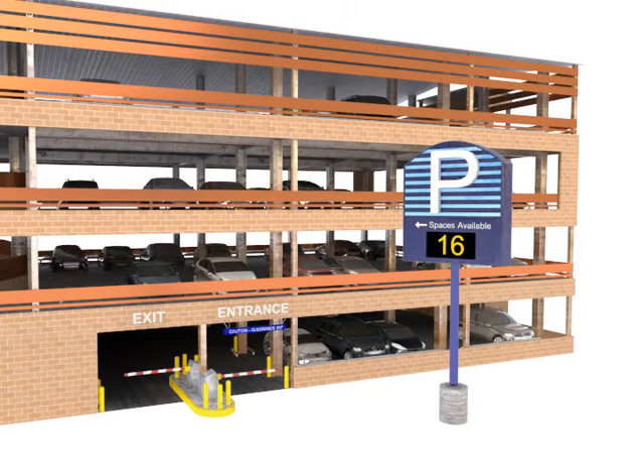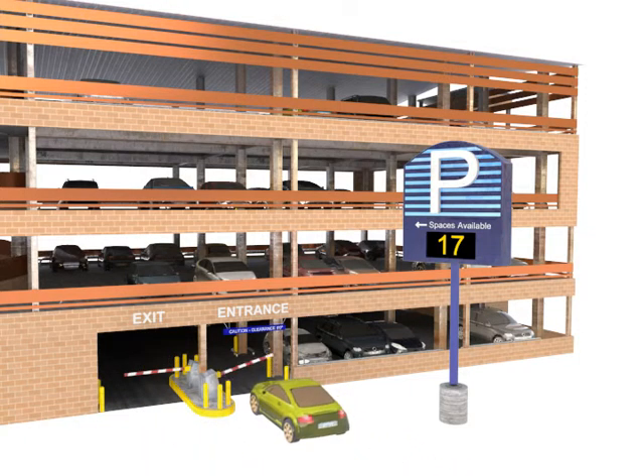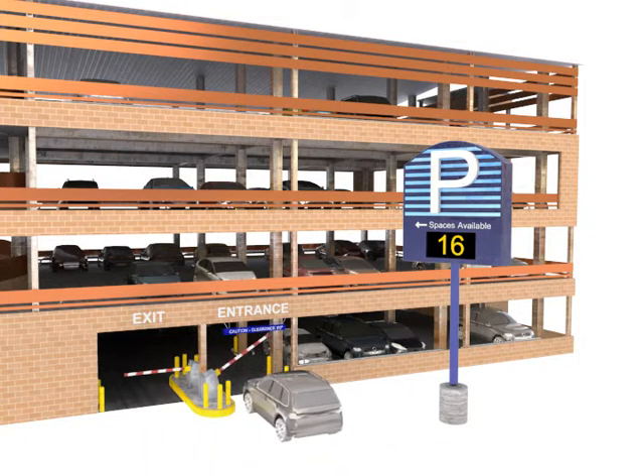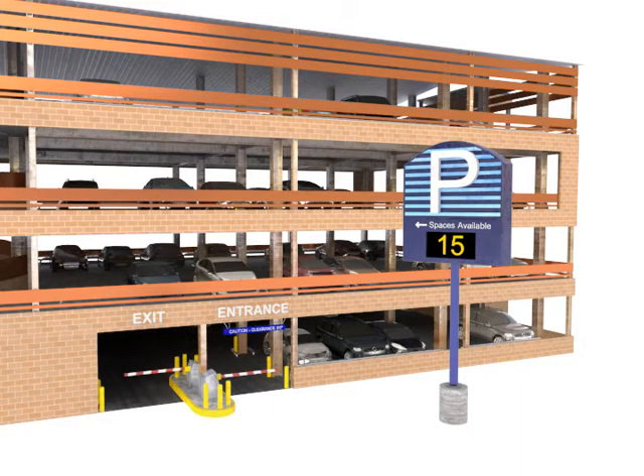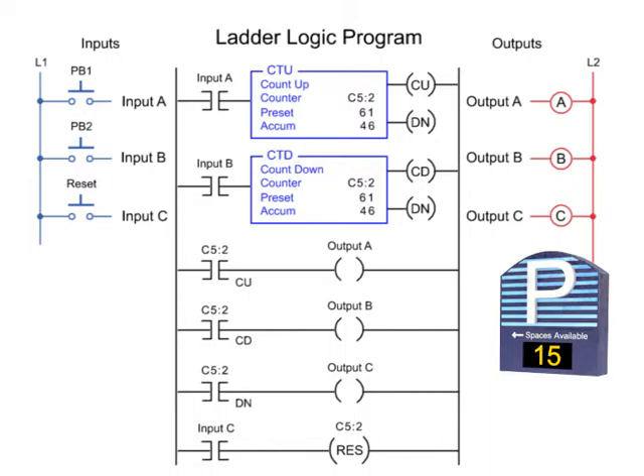Pairing a CTU and CTD in a counting sequence, using the same counter file, is demonstrated in a Parking Garage application. As vehicles enter the Parking Garage, PB1 is pressed to open the gate. The CTU instruction increments by one, and the visual display is updated.